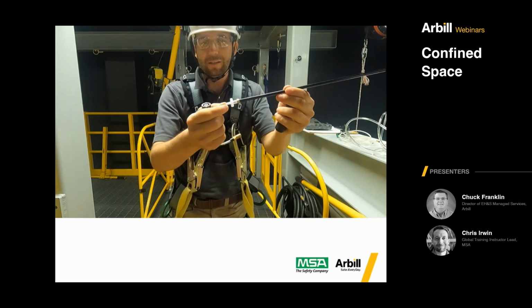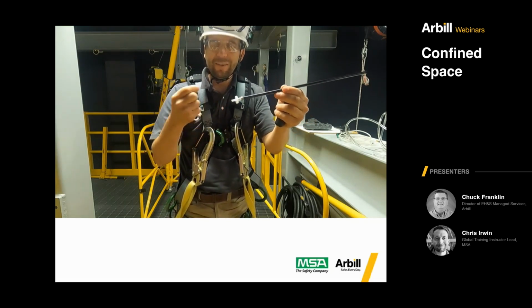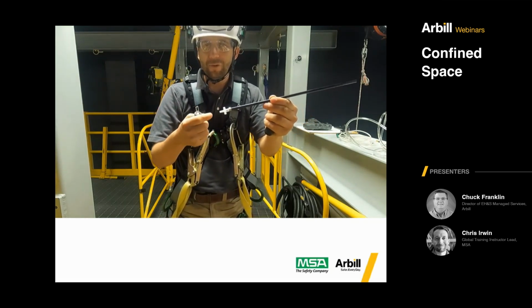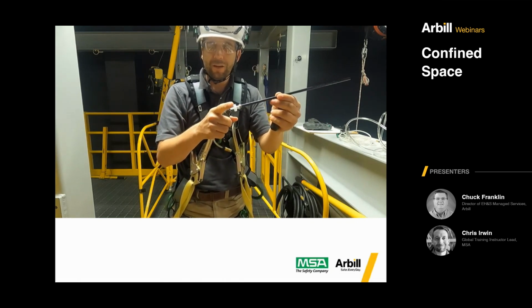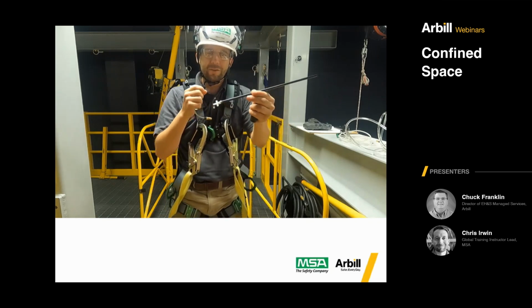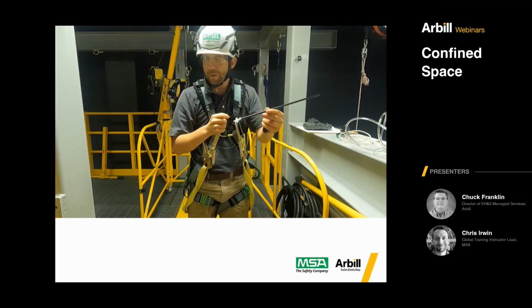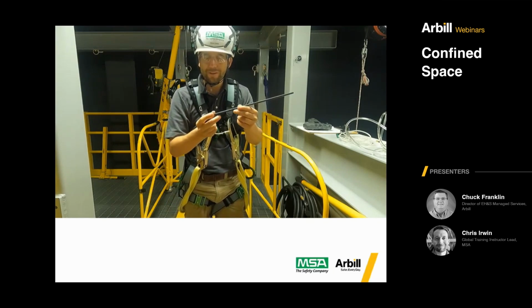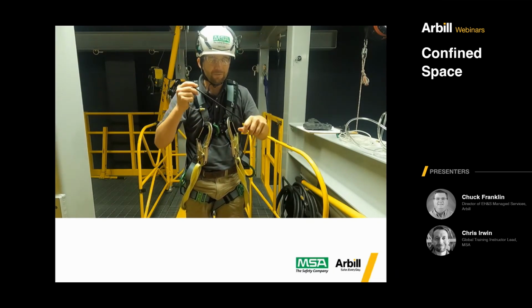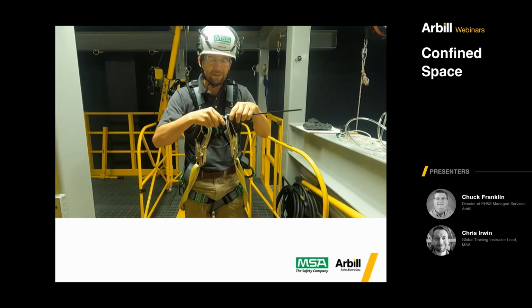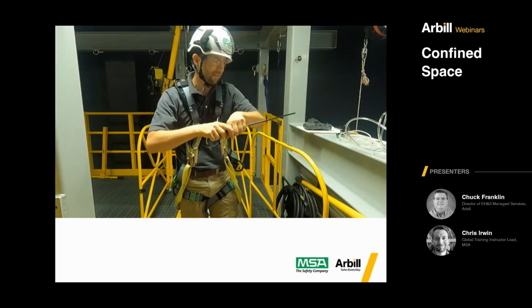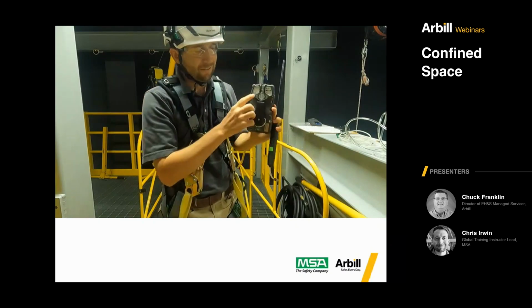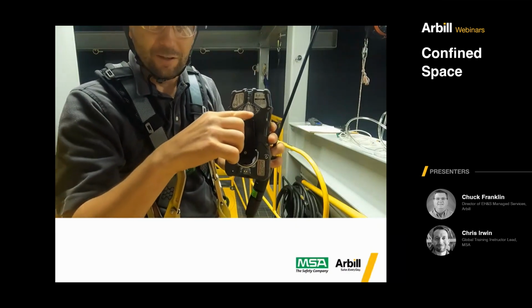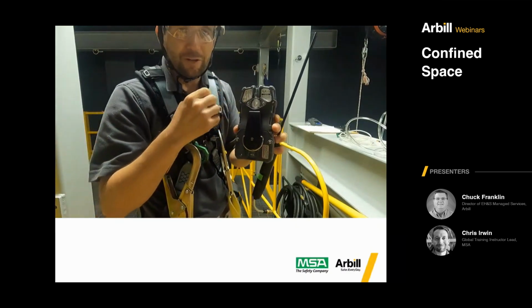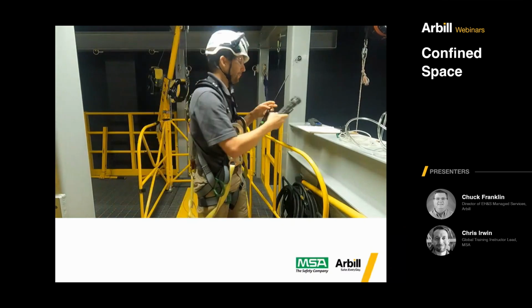Right here is a filter. If I accidentally do drop the end of this in water or a liquid, it'll get plugged up in here. So you don't want to drop it in any kind of liquid, but there is a stopgap if we accidentally do that. In fact, on the back side of the gas detector, right where the inlet is, there's a pump built into this, and right where this inlet is, there's another filter to stop any water coming through.